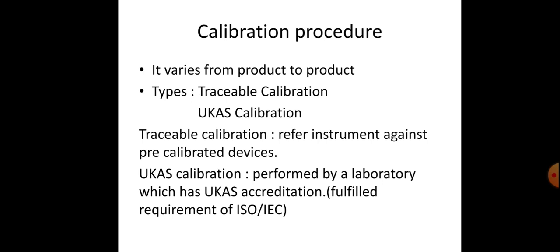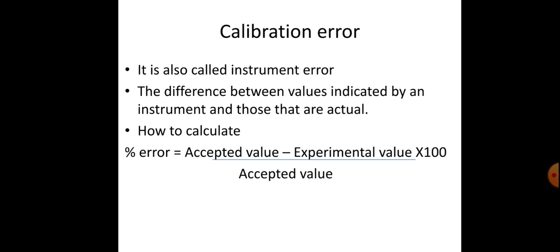The calibration procedure varies from product to product. Types of calibration: traceable calibration and UKAS calibration. Traceable calibration refers to checking an instrument against pre-calibrated devices. UKAS calibration is performed by a laboratory which has UKAS accreditation, and it fulfills the requirements of ISO or IEC.